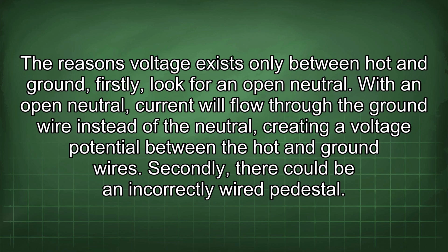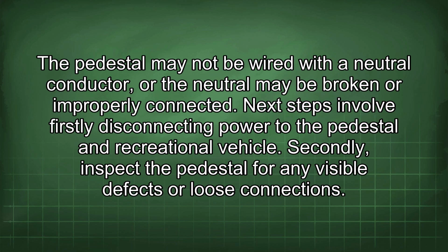The reasons voltage exists only between hot and ground: firstly, look for an open neutral. With an open neutral, current will flow through the ground wire instead of the neutral, creating a voltage potential between the hot and ground wires. Secondly, there could be an incorrectly wired pedestal. The pedestal may not be wired with the neutral conductor, or the neutral may be broken or improperly connected.